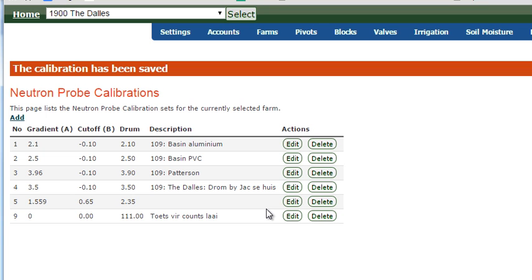The instrument can keep all of these calibrations. It can do 16 in fact, but then it means the operator needs to remember to change calibrations when it gets to a site. It is a lot better, safer to keep the instrument on one calibration, and then when you bring the data back to the software, convert from one calibration to the other as needed.